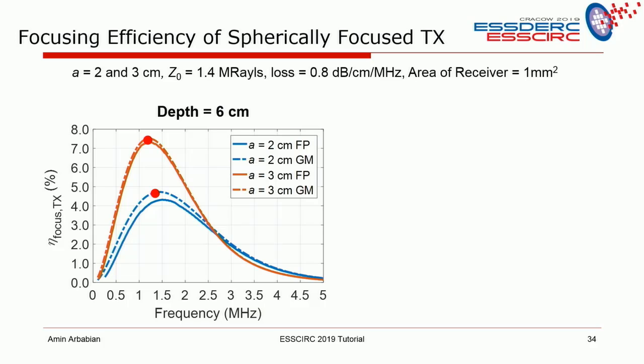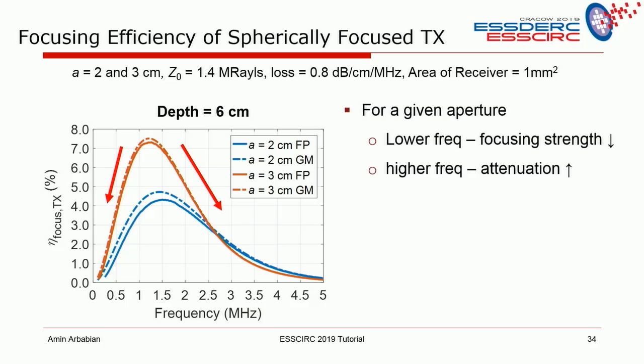But one of the things you see is that if my frequency goes down, if I go lower in frequency, I lose my focusing capability. Remember, focusing was a function of your wavelength or frequency. If your frequency is lower, I can't focus as efficiently. And if I go up in frequency, it drops because of losses. So there presents itself, given our constraints, given our dimensions, sort of an optimal frequency range. And usually for a lot of our applications, these land between 1 and 2.5 megahertz. That's sort of an optimal range.